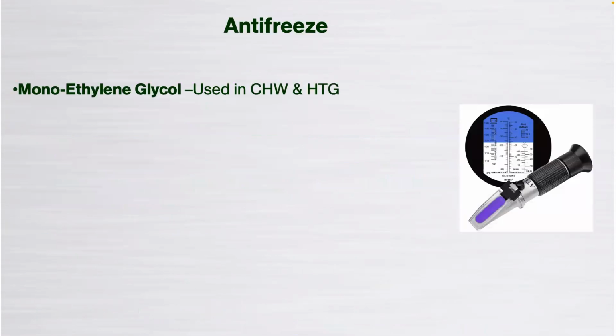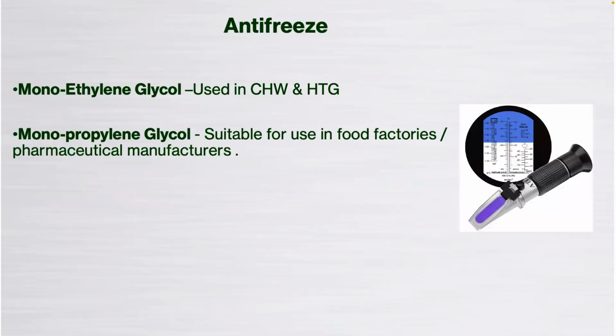Antifreeze or glycols, as they're known, there are two types typically used. So there's monoethylene, or MEG, as it's known for short. Monoethylene glycol is really the most, first of all, I would say it's the most readily available, although glycol at the moment is very difficult to come by. Prices are changing due to the market conditions, but MEG is the most commonly used one. It's more, I would say, competitive than propylene, but it is toxic. So if you're looking to be environmentally friendly, I would certainly propose not to use that and specify monopropylene glycol.